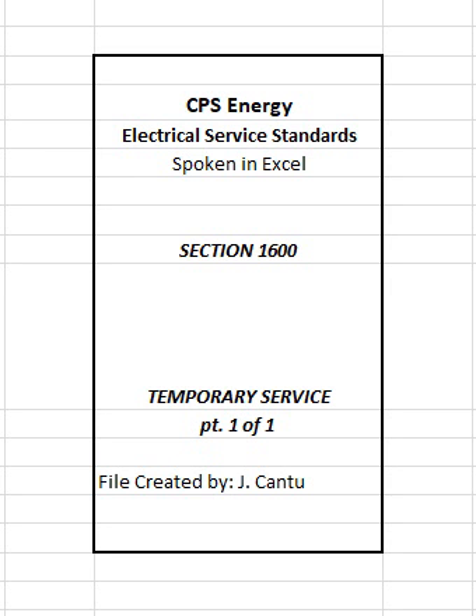1602 Construction of temporary meter structure. The temporary structure must be of sound construction. A minimum of 4-inch x 4-inch wooden mast shall be set a minimum of 2 feet in the ground and be supported by a minimum of 3 2-inch x 4-inch braces and stakes. Top braces are to be secured to temporary structure within 18 inches from top of structure for underground services or 18 inches below service head for overhead services. Refer to figures 1601 and 1602.